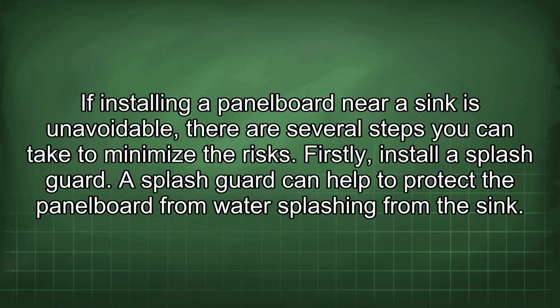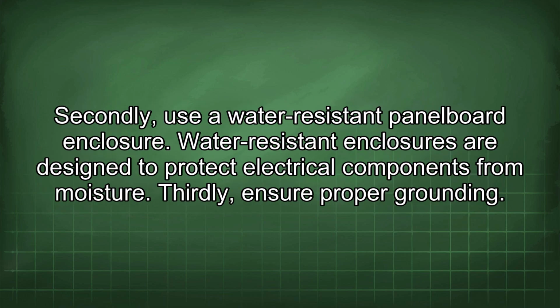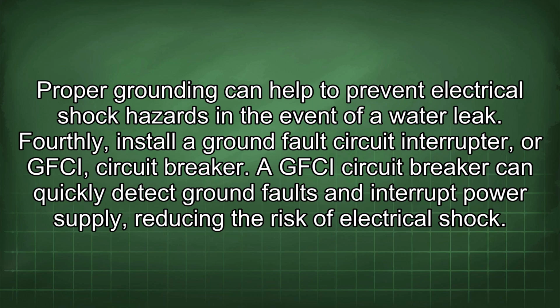If installing a panel board near a sink is unavoidable, there are several steps you can take to minimize the risks. Firstly, install a splash guard. A splash guard can help to protect the panel board from water splashing from the sink. Secondly, use a water-resistant panel board enclosure. Water-resistant enclosures are designed to protect electrical components from moisture. Thirdly, ensure proper grounding. Proper grounding can help to prevent electrical shock hazards in the event of a water leak. Fourthly, install a ground fault circuit interrupter, or GFCI, circuit breaker. A GFCI circuit breaker can quickly detect ground faults and interrupt power supply, reducing the risk of electrical shock.